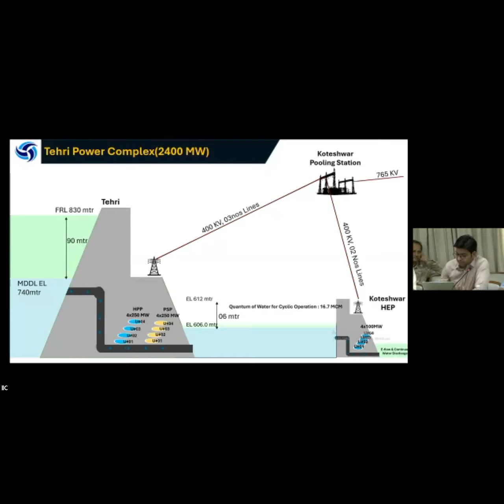These are the salient features of the Tehri PSP. Tehri PSP is an on-stream PSP because both reservoirs are located on the Bhagirathi River, and this project is equipped with India's first variable speed doubly fed asynchronous machines. It has a large net head variation from 127 meters to 227 meters. The characteristic of the doubly fed induction machine is that power can be exchanged through both rotor and stator.